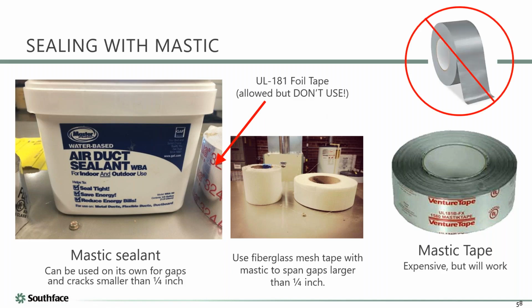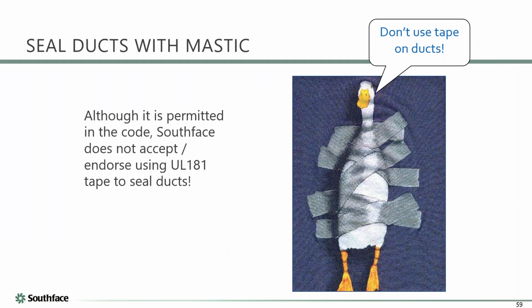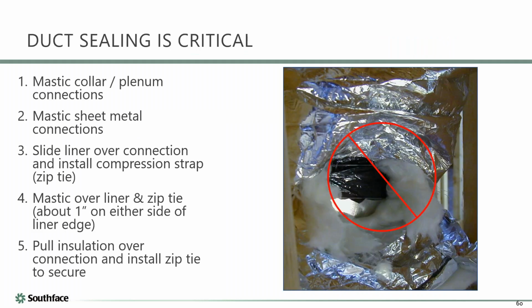And again, the one tape you absolutely cannot use is gray cloth duct tape. So mastic tape, those are okay. All right, and as our friend says, please don't put tape on ducts. Okay, all right, no one laughed, so I'm gonna drive on.